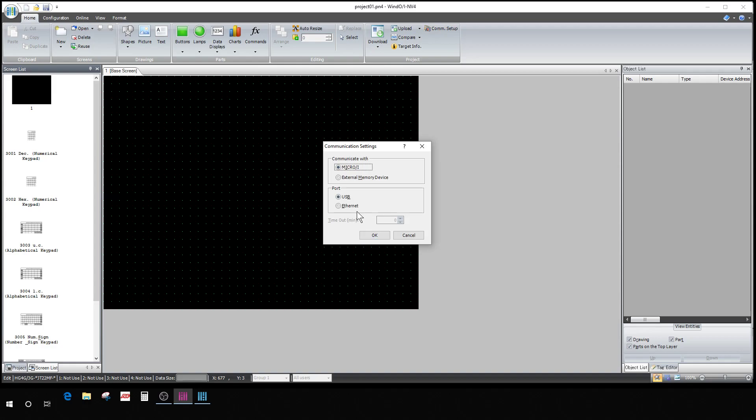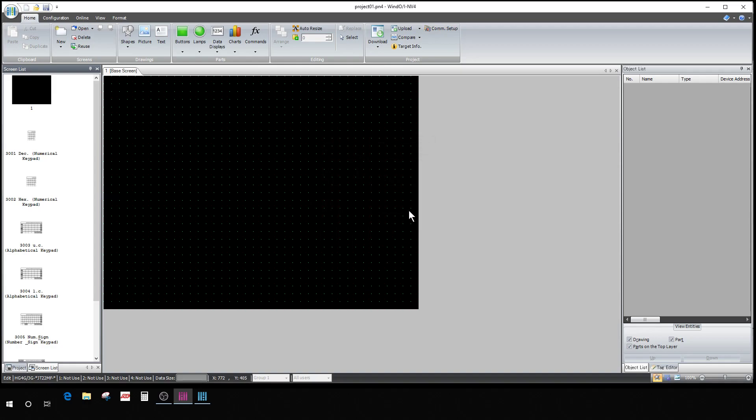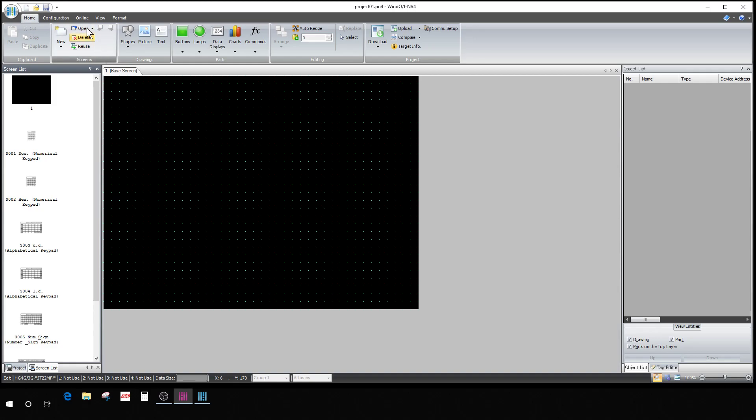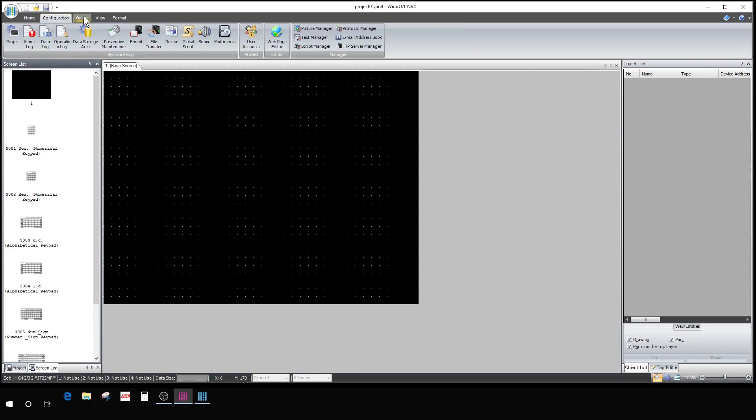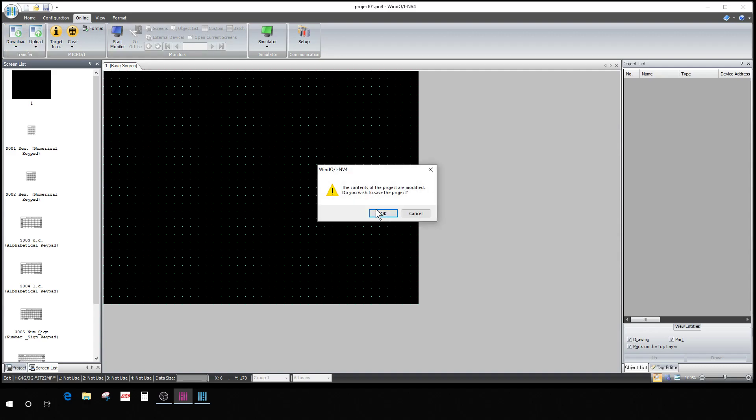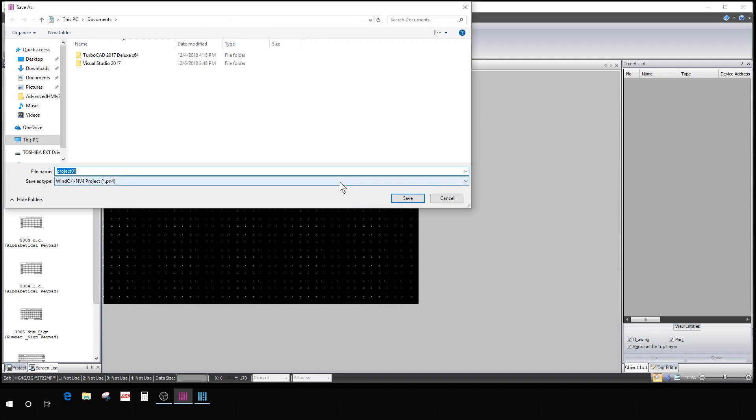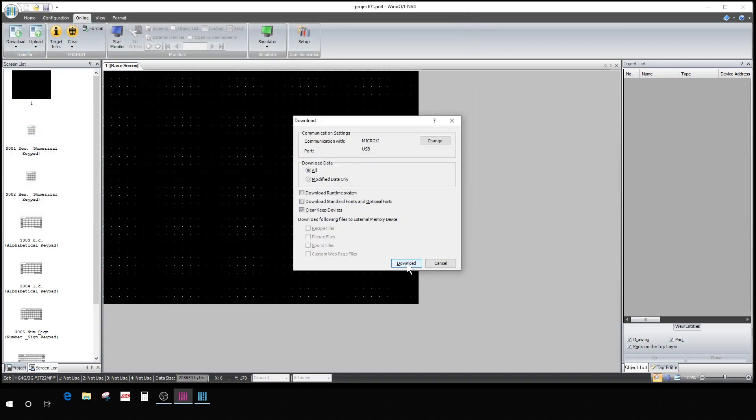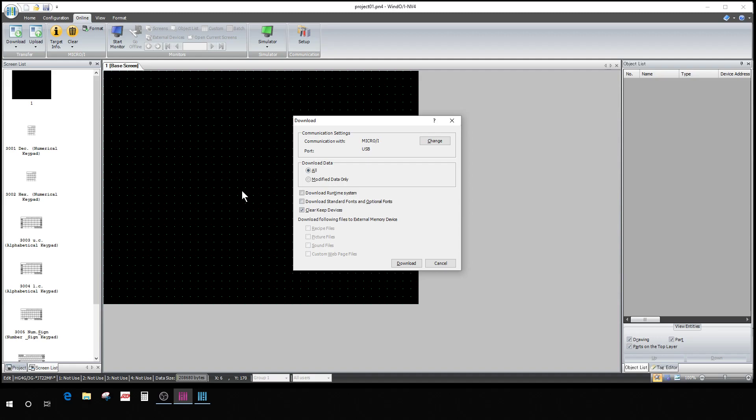Now you want to basically do the same thing for this. You have comm setup, make sure you are on USB. Click online, click okay. The same thing comes up here. You have to be connected USB to the actual HMI. You can't do pass through or none of that stuff that I know of. Same thing here: download runtime system, make sure that box is checked. That's what puts your firmware in. Then click download and it will put the new firmware in there into the HMI for you.